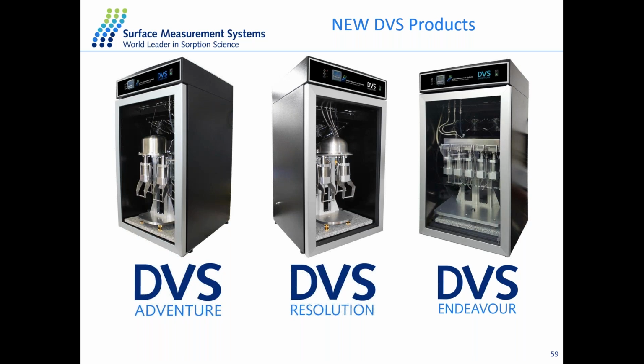Before concluding the presentation, I would like to highlight a couple of things. All the data that you have seen so far have been collected in this series of products, so DVS Adventure, Resolution, and Endeavor. The 3 products have a very similar type of incubator, which allows us to control the temperature of the experiment, and different performance from the point of view of accessories and solvent capacity. So DVS Adventure will allow you to run an experiment only in water.